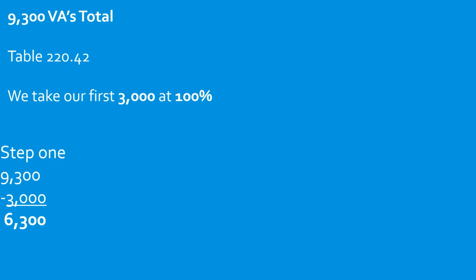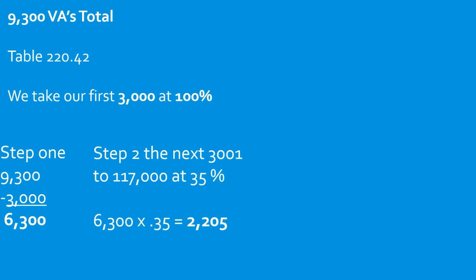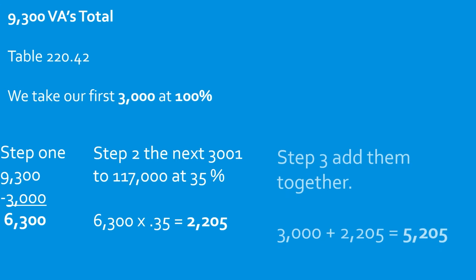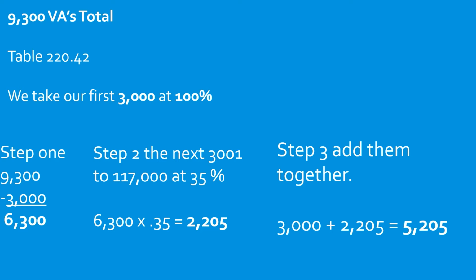Table 220.42 tells us that we take our first 3,000 at 100%. So in step 1, you take your 9,300 total minus the 3,000 that you calculate at 100%, and that gives us 6,300 VAs. Then it tells us to take the next 3,001 up to 120,000 at 35%. So we take 6,300, multiply it by 0.35, and that gives us 2,205 VAs. Then, step 3, we add them together. We take 3,000 and add the 2,205 VAs, and that gives us 5,205 VAs. So we select D.